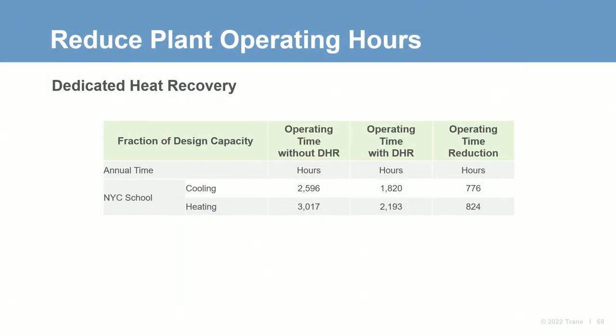Applying dedicated heat recovery chillers can reduce the time when multiple air-to-water heat pump units need to operate for simultaneous cooling and heating. The table shown here, which refers back to our school example, shows heat pump operating hours are reduced by up to a total of 1,600 hours per year. By recovering energy from one loop to the other, the heat recovery chiller can fully meet one required load and partially meet the other. A single air-to-water heat pump unit meets the remainder of the dominant loop's load. This can help stabilize operation and extend the heat pump unit's operating life. Heat recovery is almost always worth evaluating when a reasonable simultaneous load is available. It can be utilized to reduce energy use, lower the life cycle cost of the system, extend equipment life, increase system reliability, and may even be required by code.